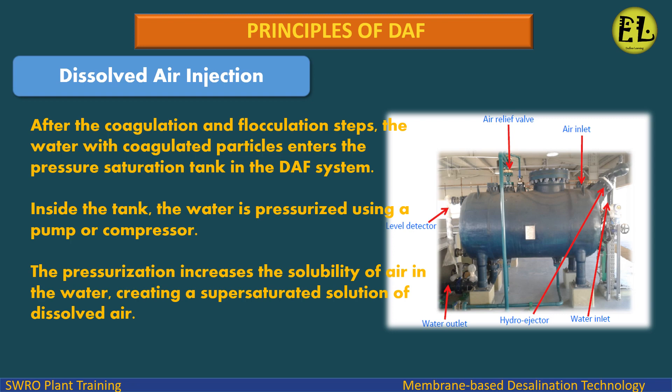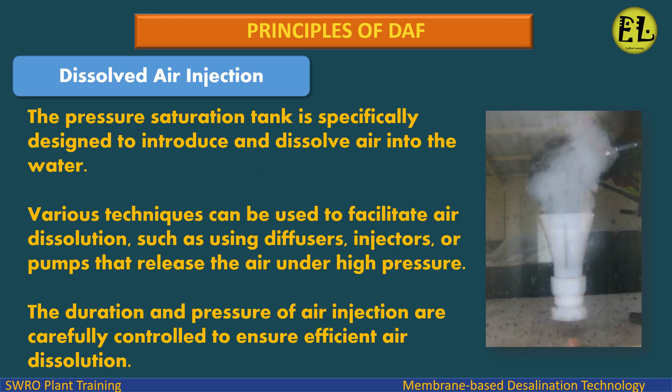Dissolved air injection: After the coagulation and flocculation steps, the water with coagulated particles enters the pressure saturation tank in the DAF system. Inside the tank, the water is pressurized using a pump or compressor. The pressurization increases the solubility of air in the water, creating a supersaturated solution of dissolved air. The pressure saturation tank is specifically designed to introduce and dissolve air into the water. Various techniques can be used to facilitate air dissolution, such as using diffusers, injectors, or pumps that release air under high pressure. The duration and pressure of air injection are carefully controlled to ensure efficient air dissolution.